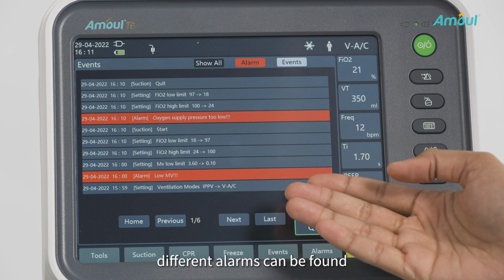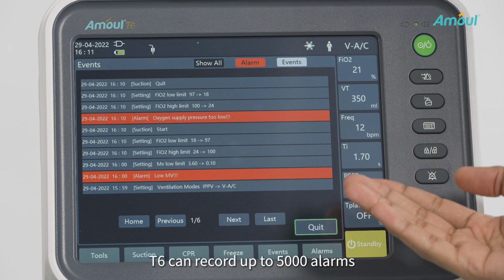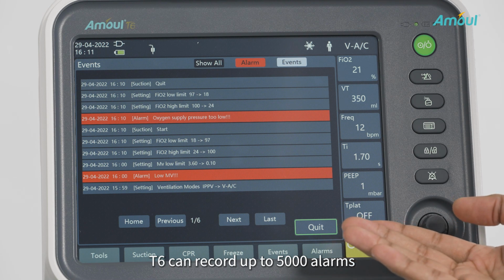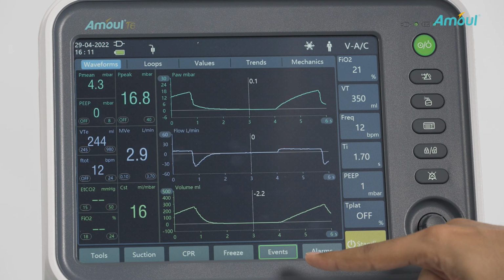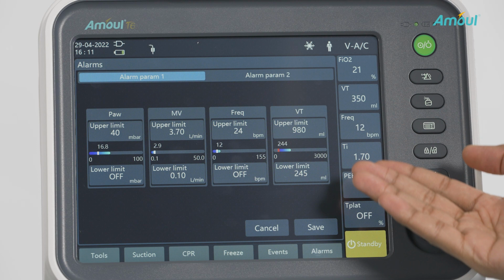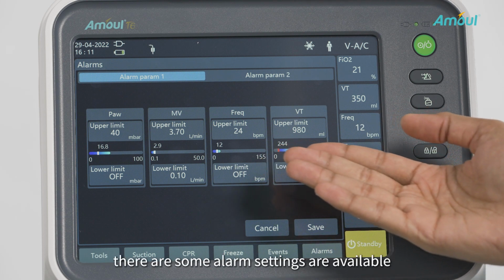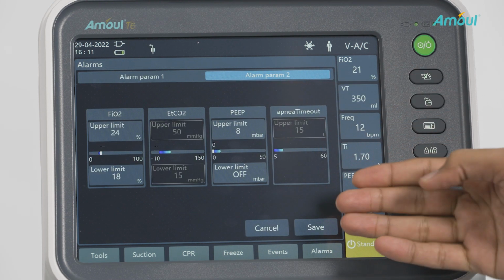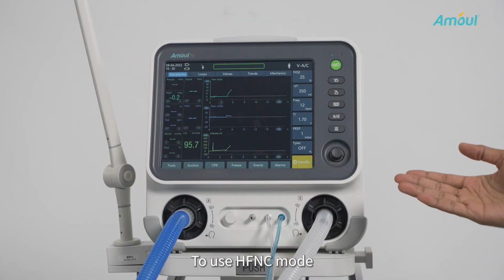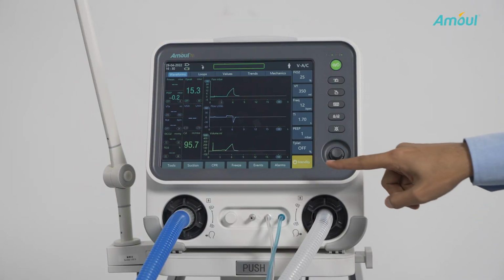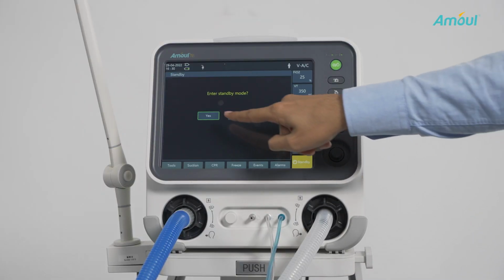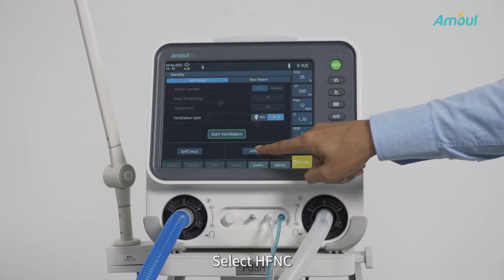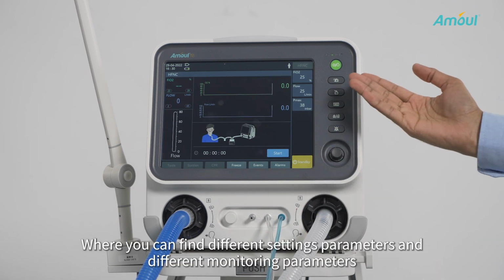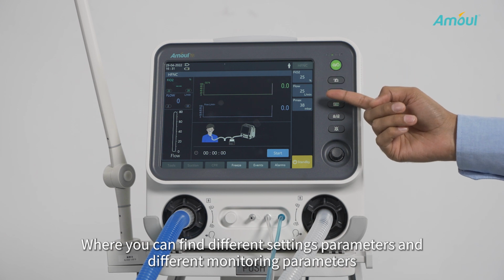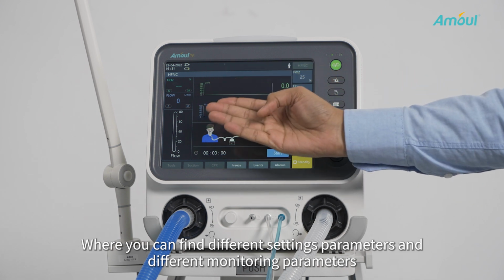And in the events, different alarms can be found. T6 can record up to 5,000 alarms. And in the alarm section, there are some alarm settings available. To use HFNC mode, switch to standby. Select HFNC, where you can find different setting parameters and different monitoring parameters.